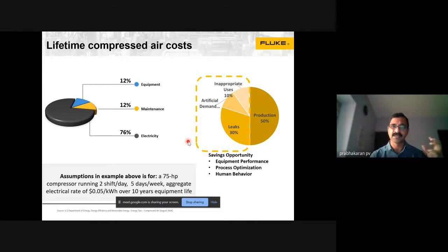Interestingly, compressed air gets misused or lost throughout the process. Only 50% of the compressed air generated by compressor systems in a facility actually goes into real production. 10% is artificial demand, meaning because of leaks and other issues, you may have to jack up production to compensate. Another 10% goes into inappropriate use.